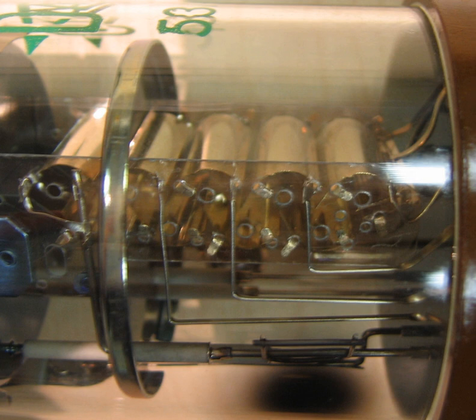The electron multiplier consists of a number of electrodes called dynodes. Each dynode is held at a more positive potential, by approximately 100 volts, than the preceding one. A primary electron leaves the photocathode with the energy of the incoming photon, or about three electron volts for blue photons, minus the work function of the photocathode.